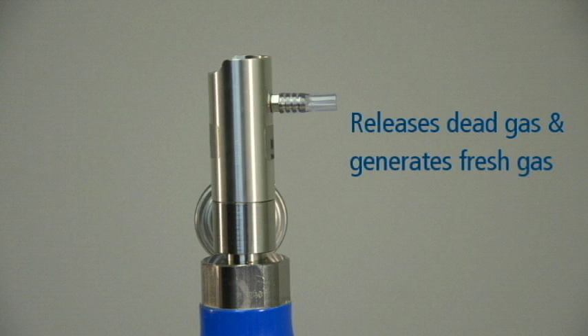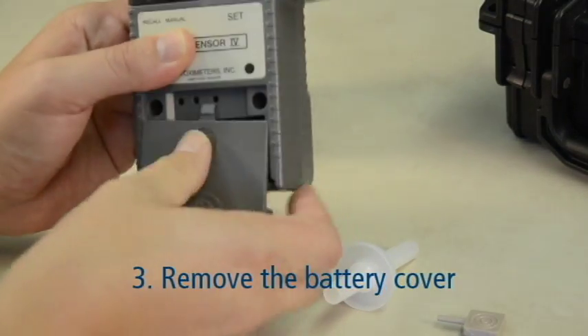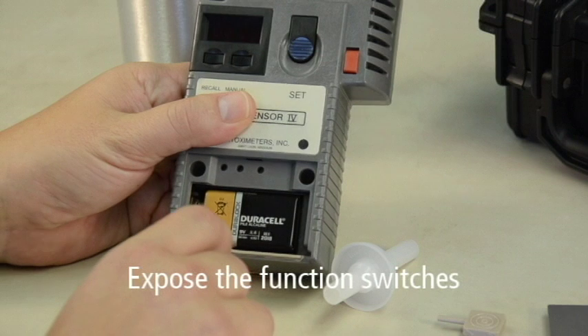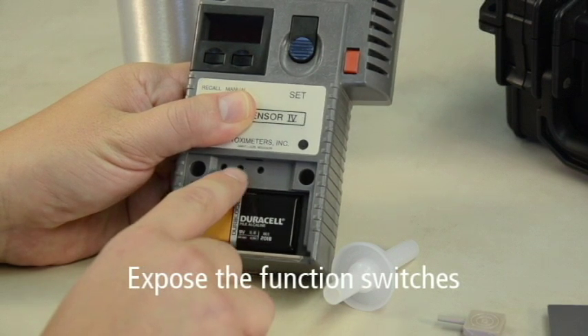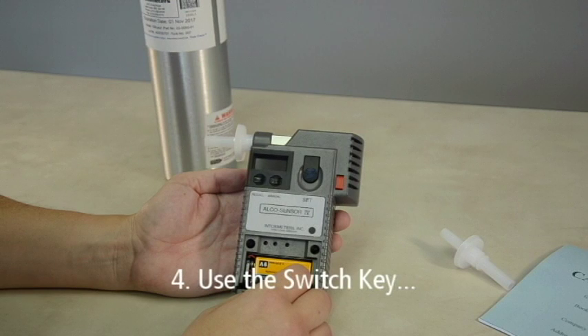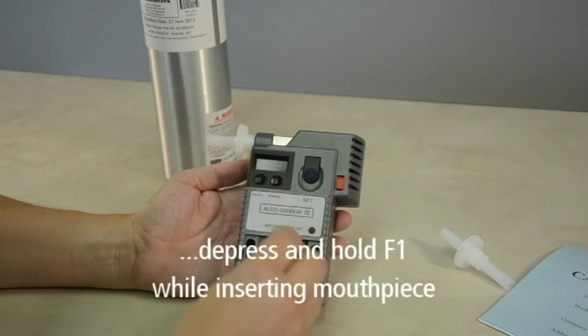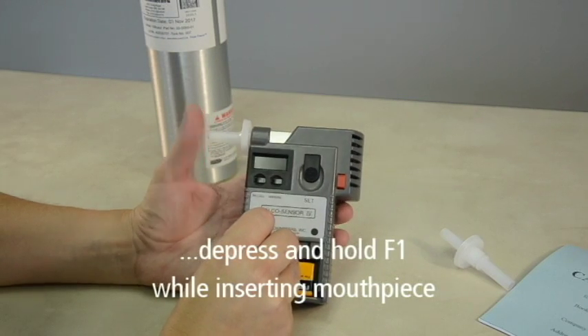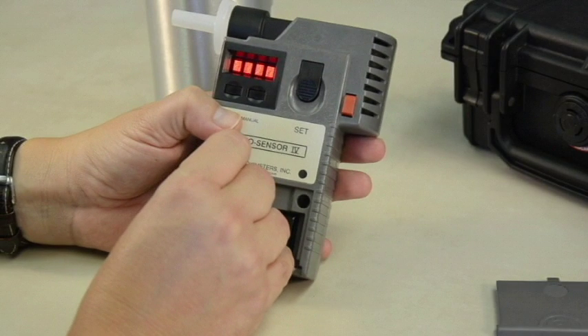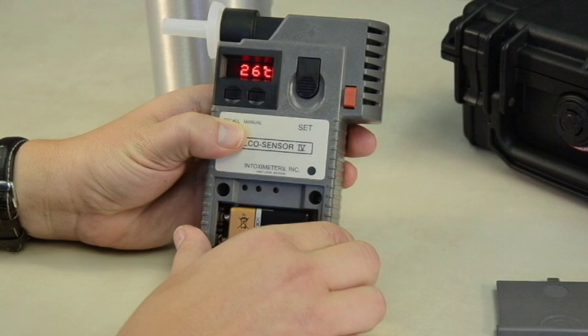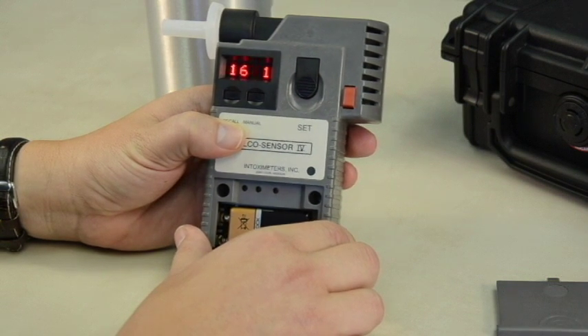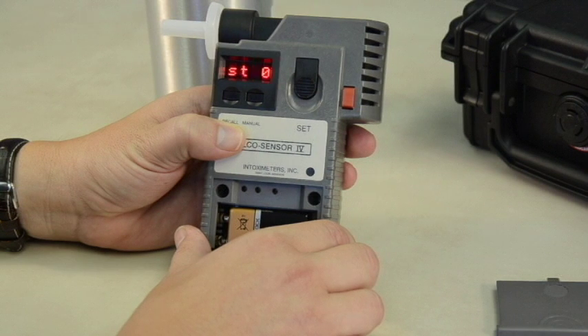Next, remove the battery cover located on the front of the device to expose the function switches, and if necessary, remove any security tape covering the holes. Using the switch key, depress and hold F1, which is the far left hole, while inserting a new mouthpiece. 4 solid blocks will appear on the display. Now release the switch key from F1. The temperature, date, time, and a 4-digit test number will scroll across the display window. The temperature must be between 23 and 27 degrees Celsius. After the 4-digit test number has appeared twice, the display will flash back and forth arrow signs.